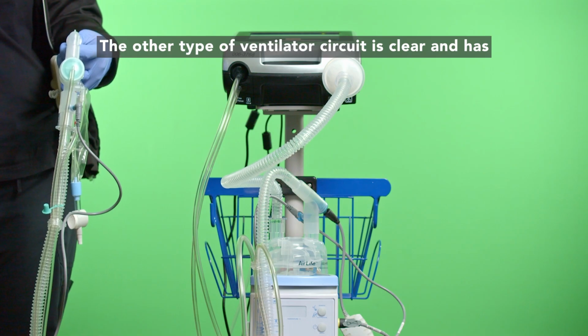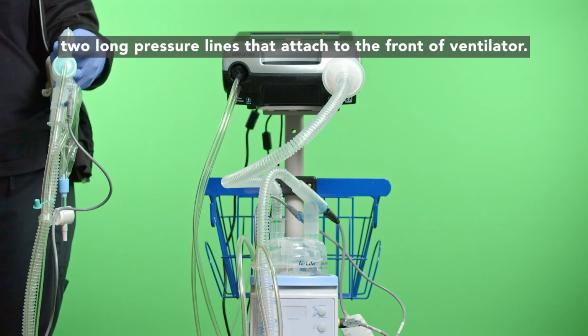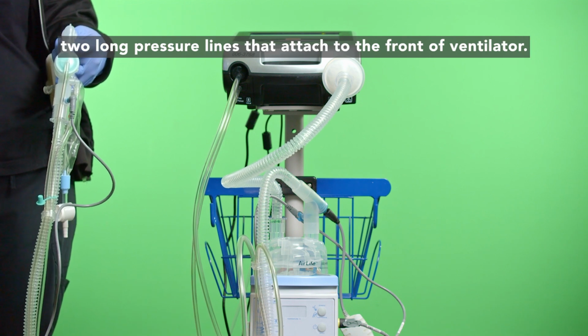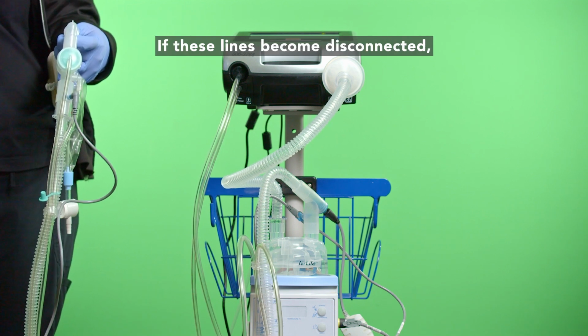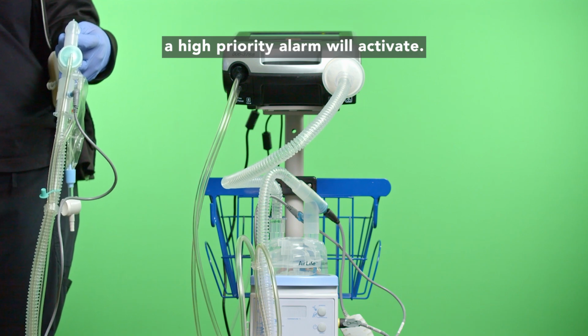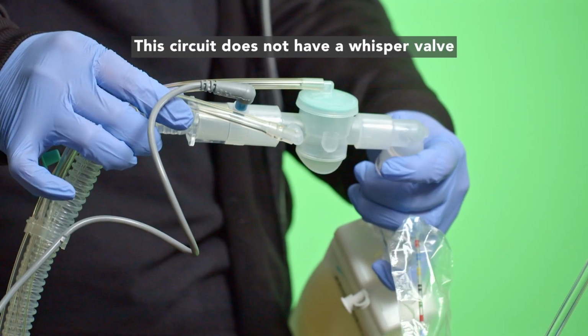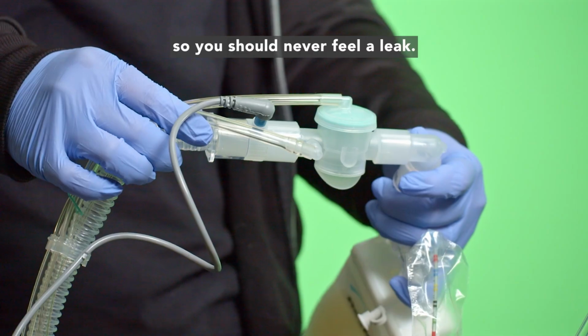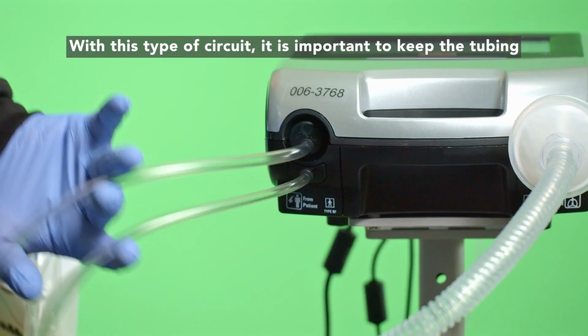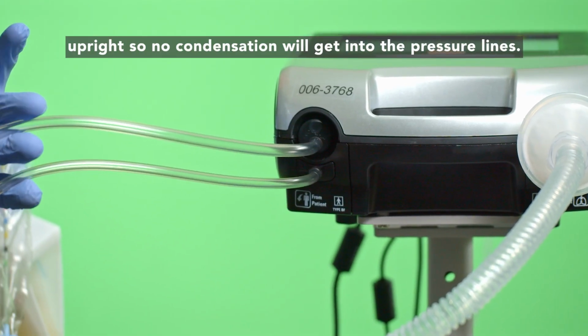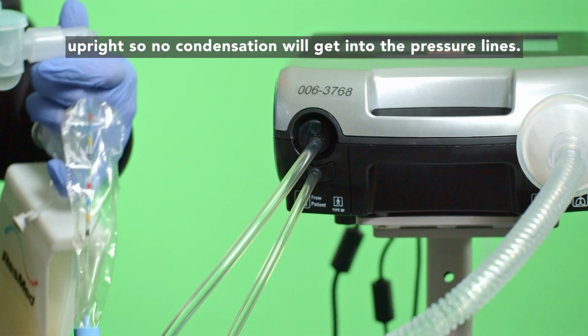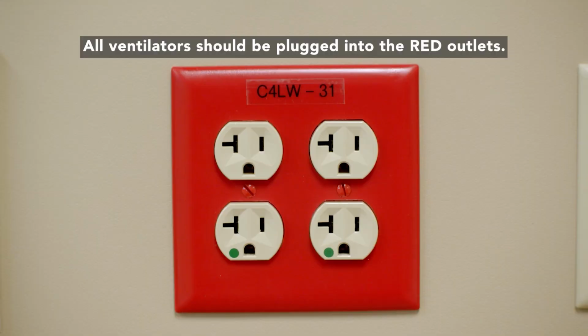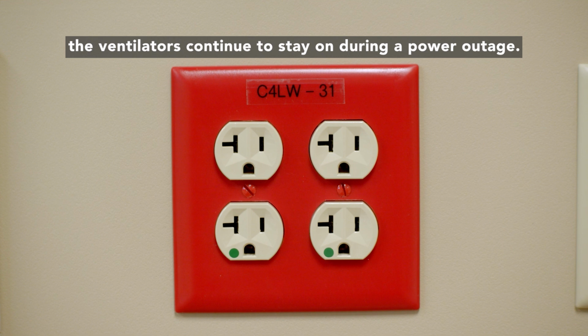The other type of ventilator circuit is clear and has two long pressure lines that attach to the front of the ventilator. If these lines become disconnected, a high priority alarm will activate. This circuit does not have a whisper valve, so you should never feel a leak. With this type of circuit, it is important to keep the tubing upright so no condensation will get into the pressure lines. All ventilators should be plugged into the red outlets. The red outlets are connected to a generator and ensure the ventilators continue to stay on during a power outage.